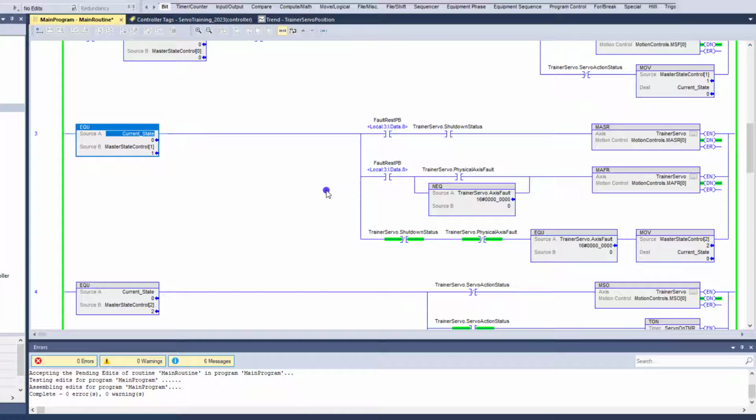Automatically resetting a fault on a servo to me is inducing danger or a hazard, because you could potentially cause movement if something were actually wrong with the system, or maybe somebody is working on the system or something of that nature. So just always know that you need to intervene, and these are the intentions behind this simple controls and simple illustration of what I'm doing.